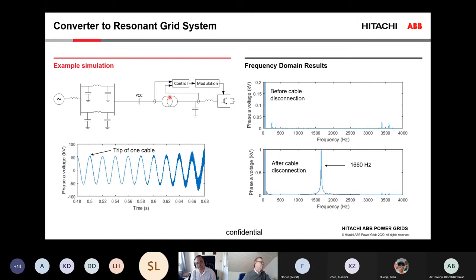If I run a simulation of this system, here you can see the phase A voltage measured at the PCC, and it starts nicely. We expect to have a sinusoidal with 50 or 60 hertz. And at this point, I disconnect one of those two cables. We can see that when I do the disconnection, there is a little bit of transient, but everything looks fine. We go back to something that looks normal, but slowly we can see there is something, a harmonic component, growing.